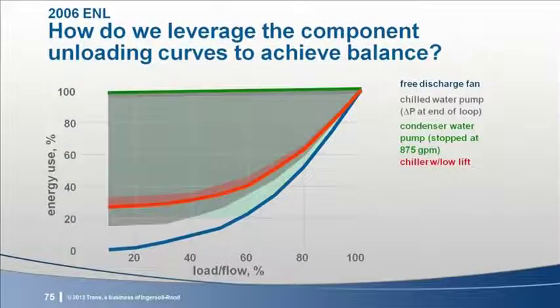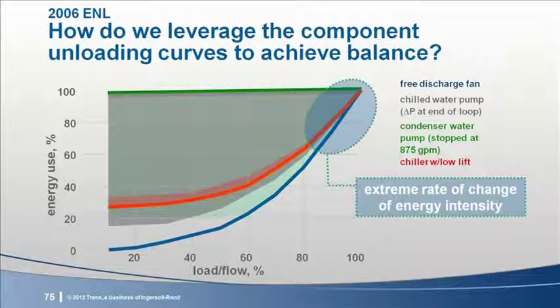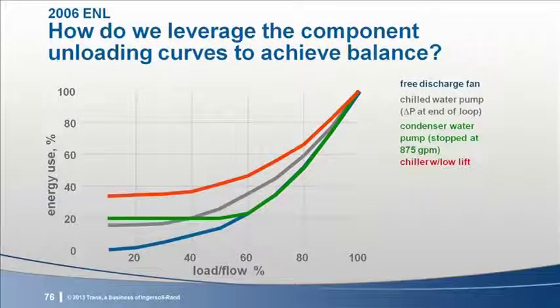This control sequence does not take advantage of the opportunity of the rapidly decreasing fan and pump energy intensity in the 100 to 80% speed range. The chiller's limited decrease in power use cannot compensate for the rapid increase in fan and pump energy use in this range. What if the control sequence slowed the condenser pump significantly with a cooling tower fan set point of 85 degrees? The pump and fan power would drop at most loads.